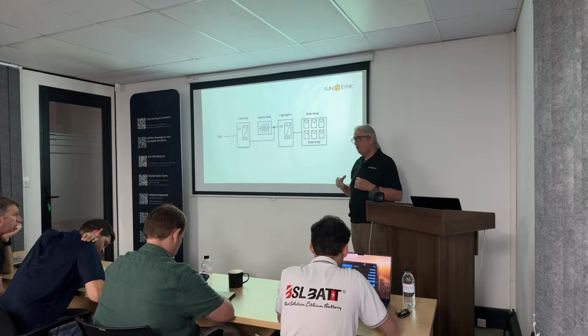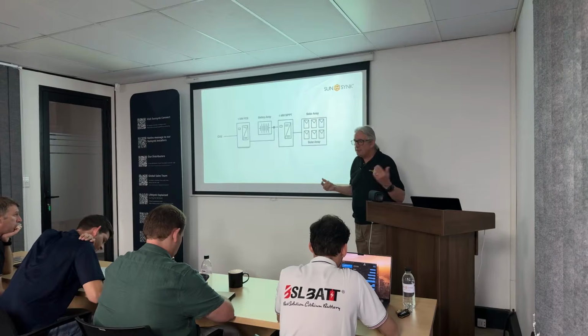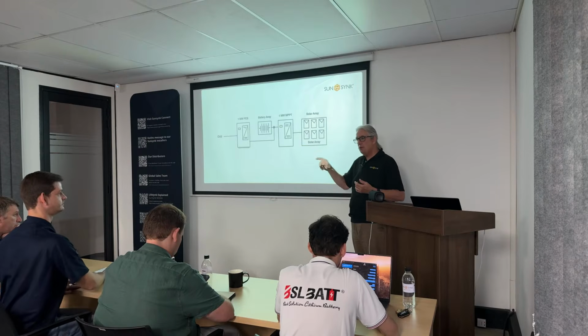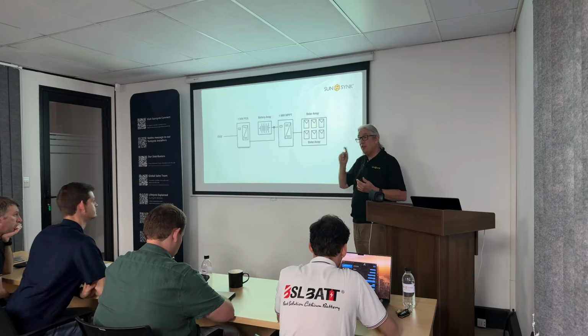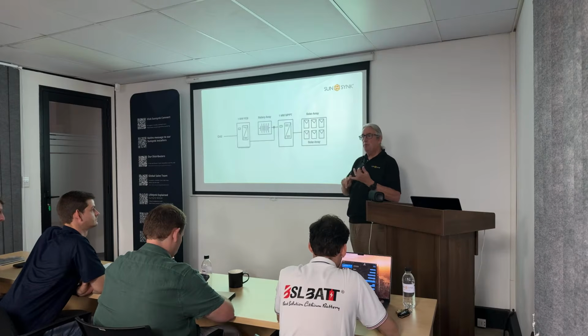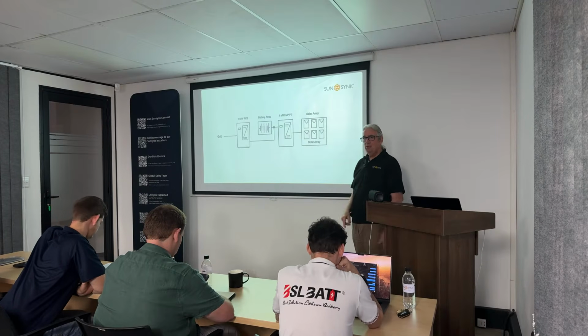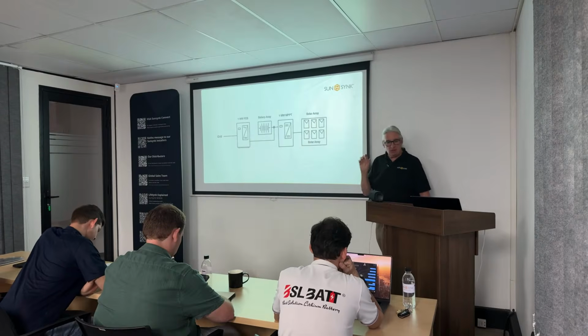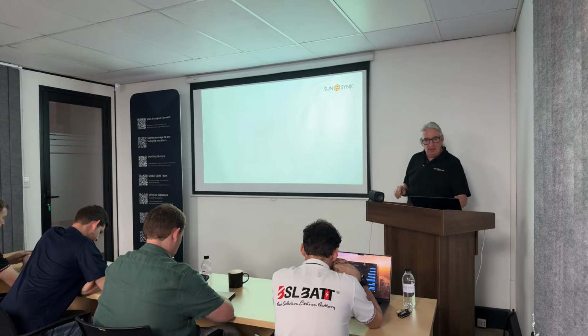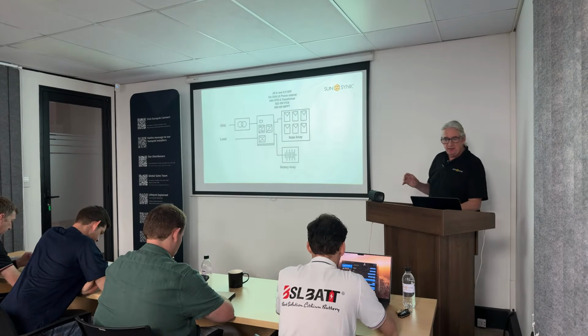So if your voltage is 400 or 440 volts, whatever it is, then it's 1.4 times the battery times the AC voltage. That's in delta. In star, it's 1.4 times 230 times 2. So it's slightly different calculations. So the batteries are larger. Just very quickly showing different configurations.